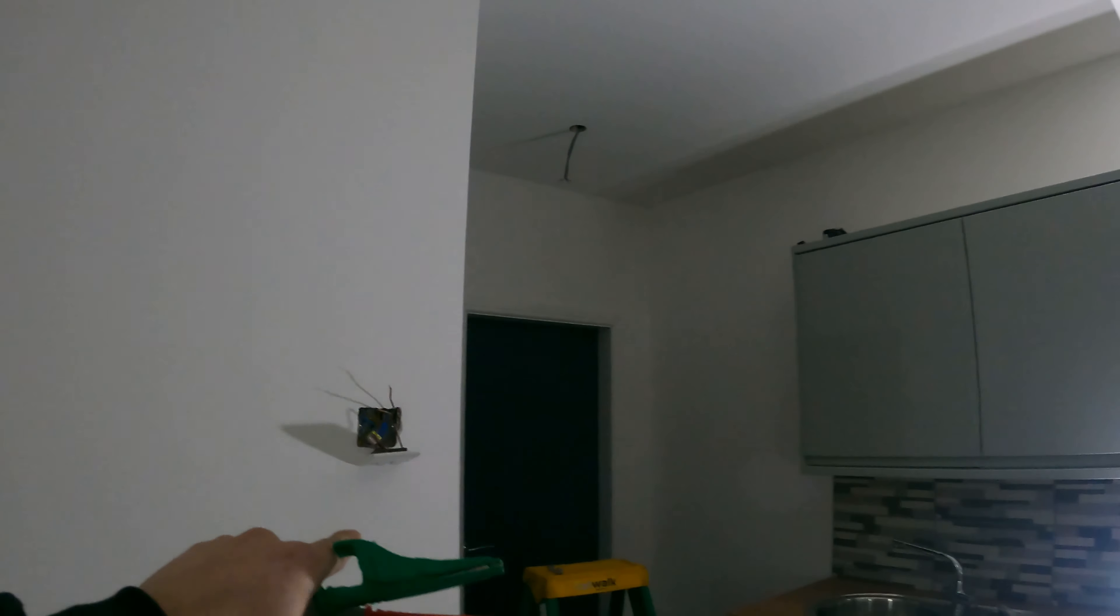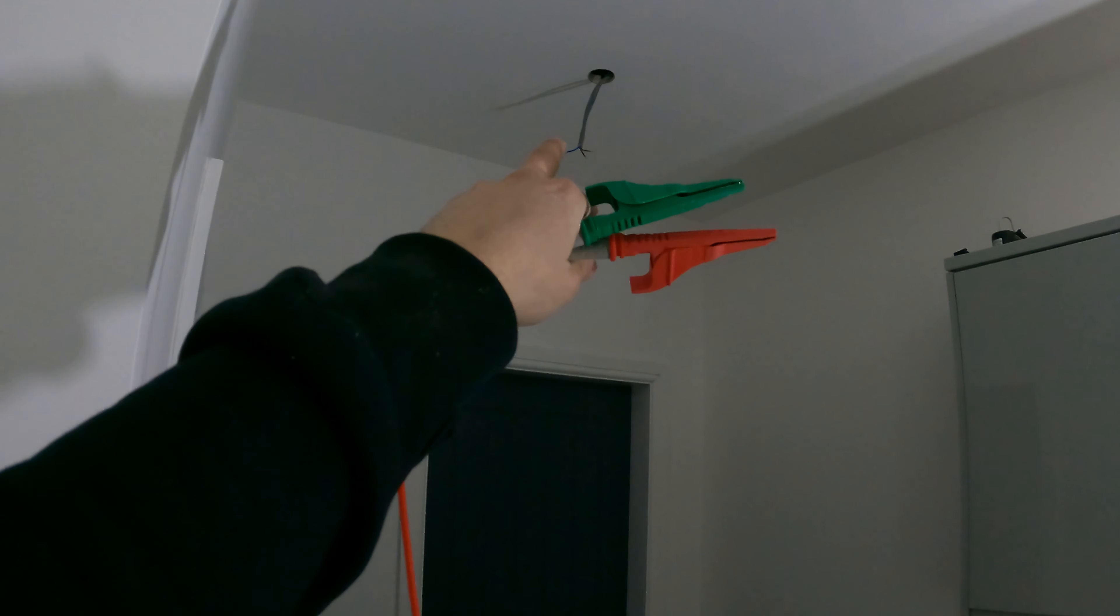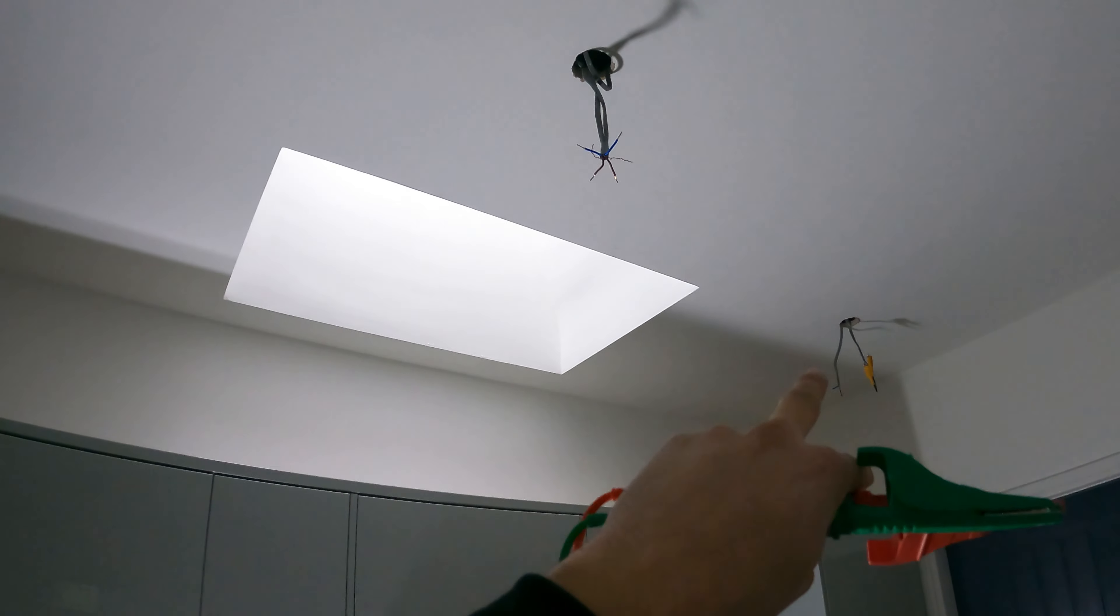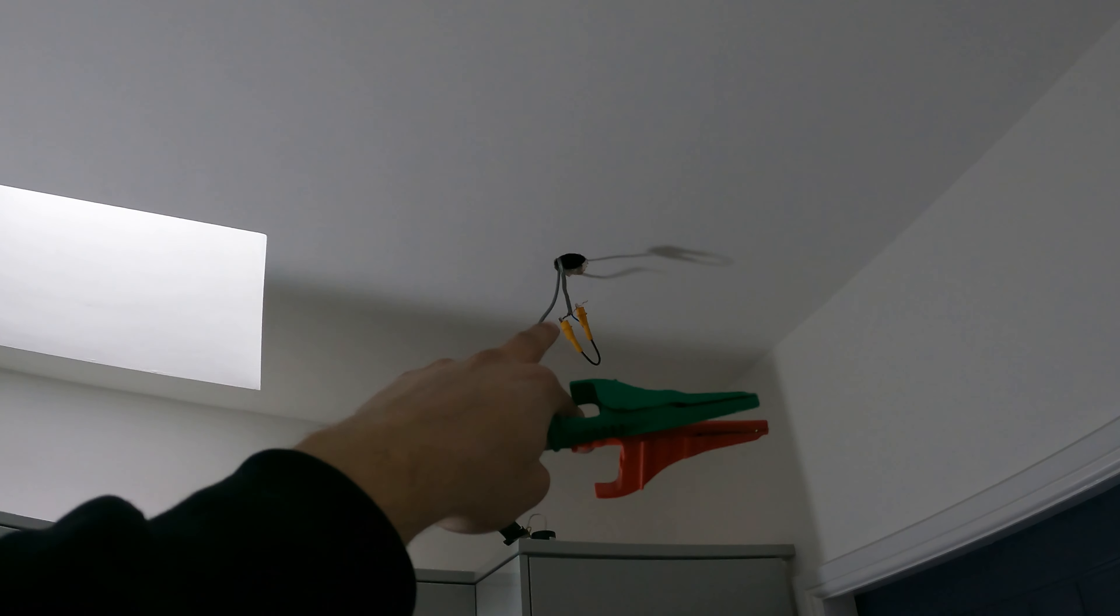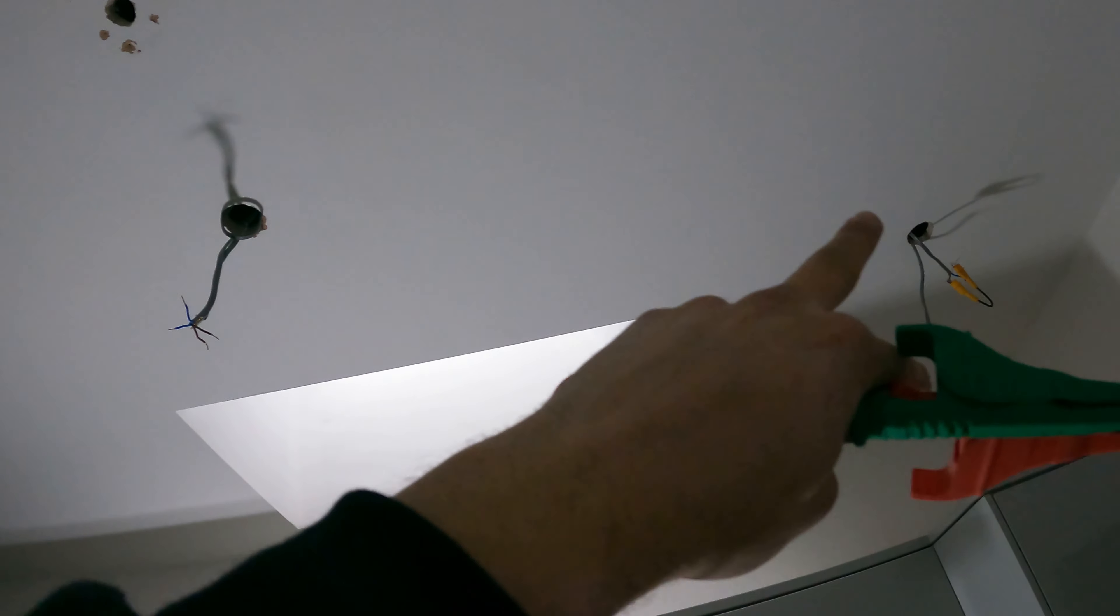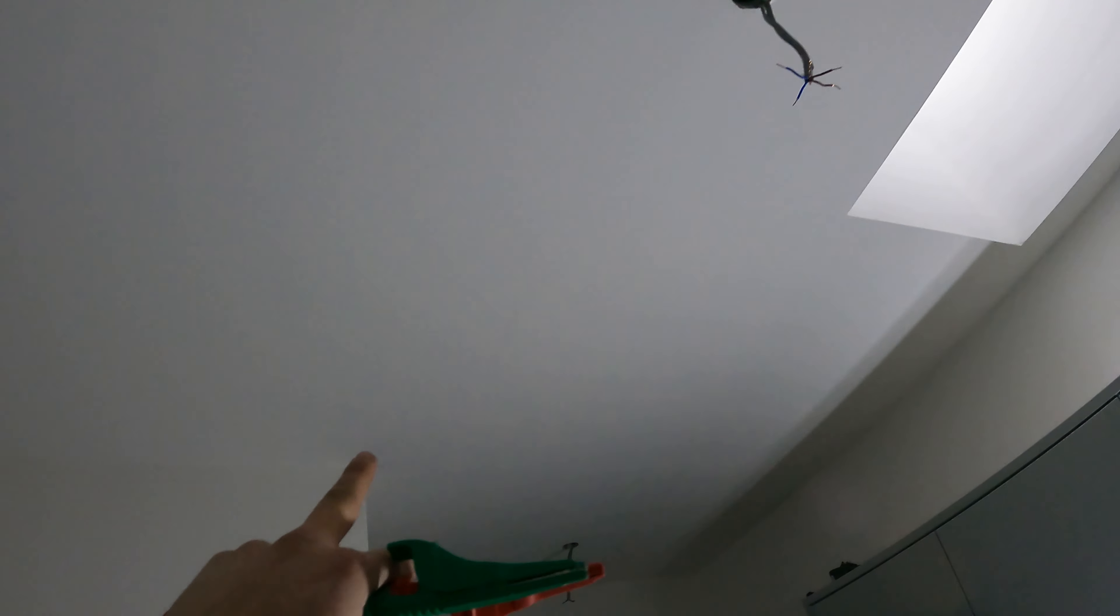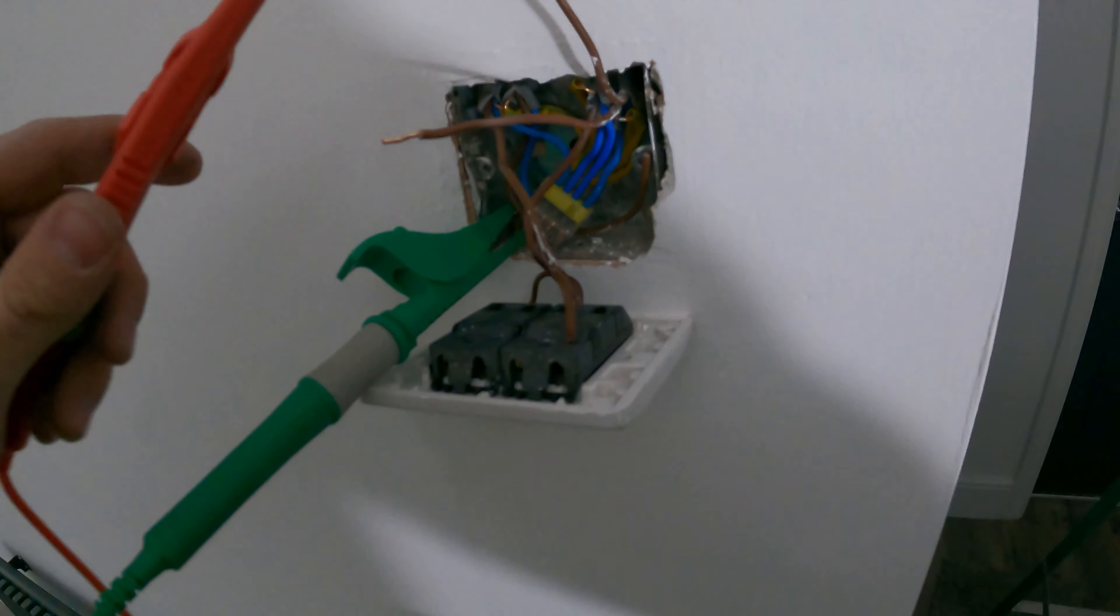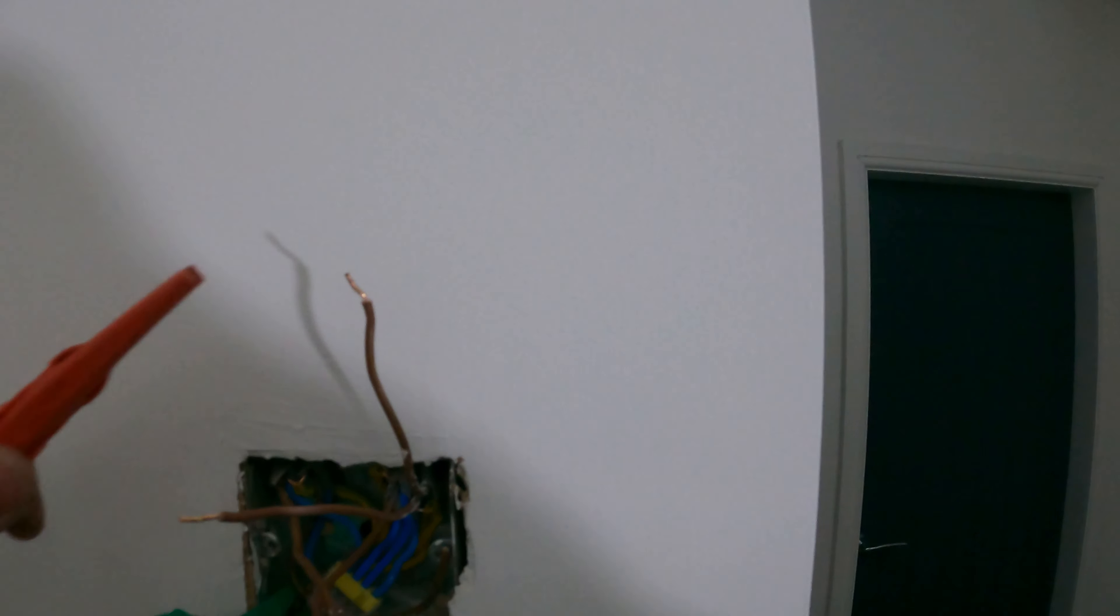Right, so where we are at right now. I've disconnected the two legs of the ring—I'm calling it a ring because it is a ring, it just shouldn't be. I've disconnected them, completely separated all the cores. This one here where I've got my jump leads on there, I've got my jump leads between the line and the earth. That cable is that one there that's sort of looped out that I've found above there. This comes down to here. So if we just clamp onto the earth there—just get onto the earth. I've got the megger set to continuity and I've got the audio on it, so you can get a bit of an audible example. This is the one that it isn't. That's not that. That one goes up to that light, as expected.